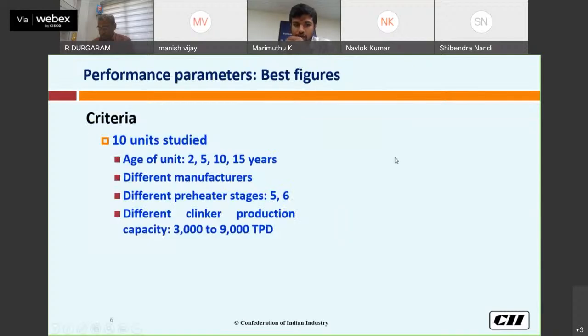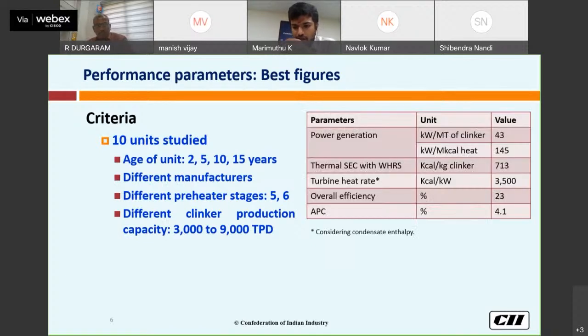Next is on the performance parameters, meaning the best figures. To find out the potential in the waste heat recovery system and to find its performance, we conducted a study in 6 to 10 units. Based on that, we arrived at the best figures from those units. The criteria we considered were the age of the unit, between 2, 5, 10, 15 years, different manufacturers, 5-stage or 6-stage preheater, and different clinker production.